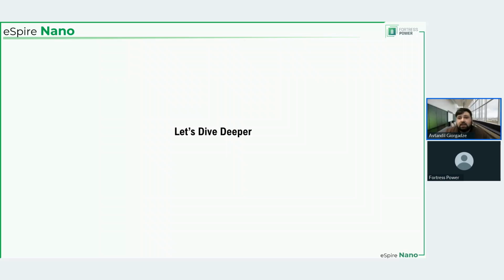One example that comes to mind is currently we're not allowing the ATS and the generator being upstream of the inverter and connecting the ATS output to the grid ports. Currently, that is the rule, but at some point that may change. Again, I don't know whether or not it will. I don't know how soon it will, but it will only change if we have tests performed and confirmed to ourselves that yes, this can be done, such that the user experience will not be bad or unsafe and so forth.